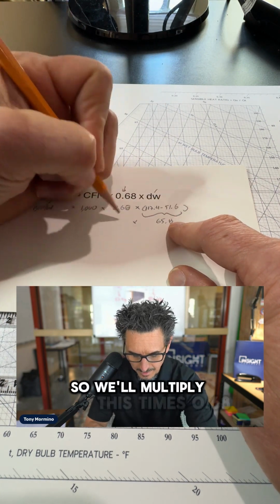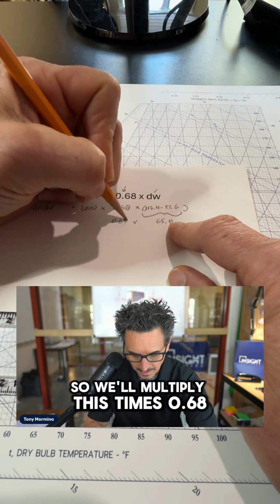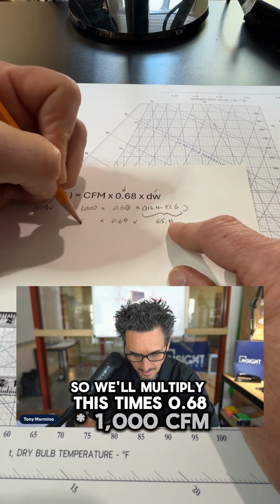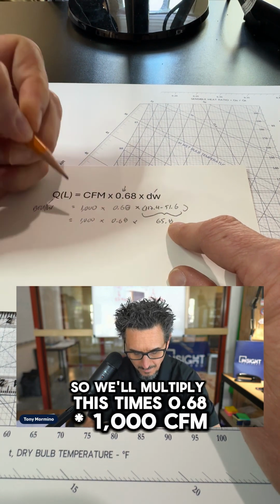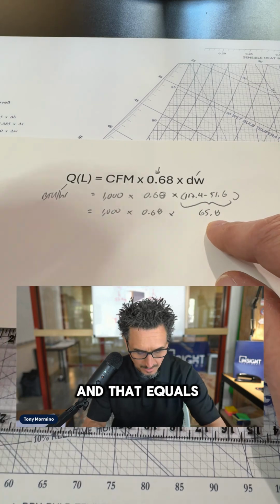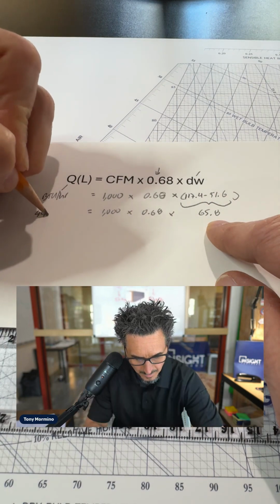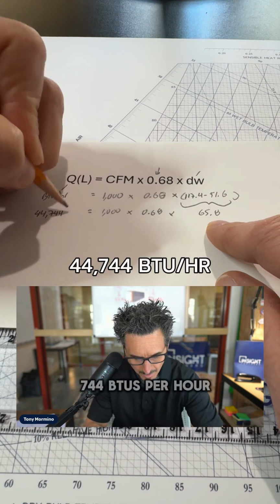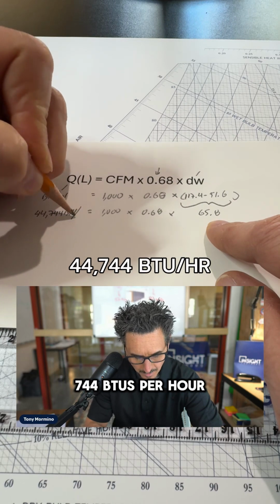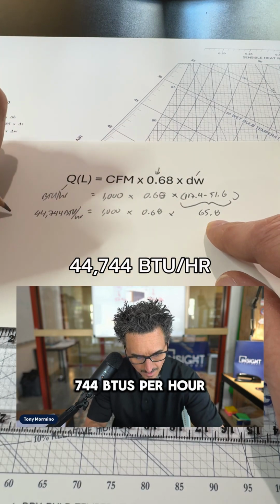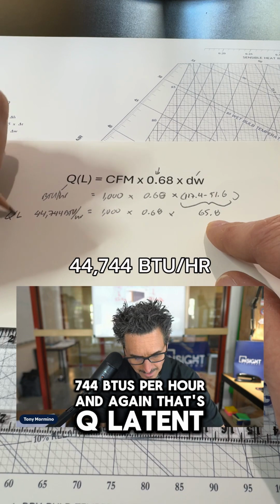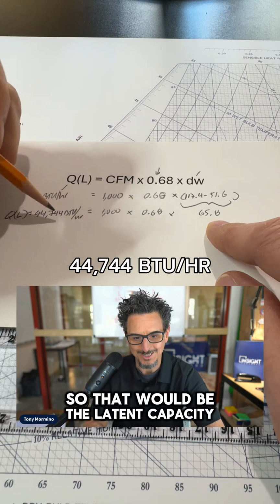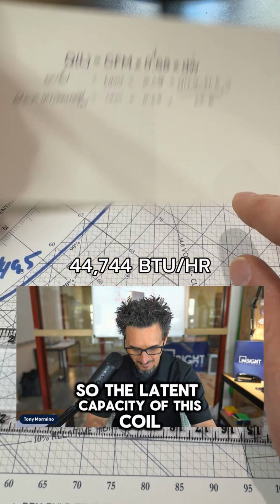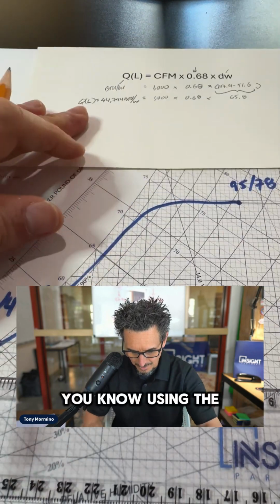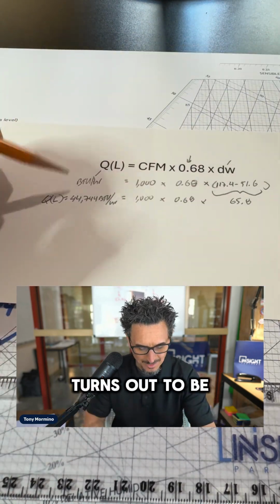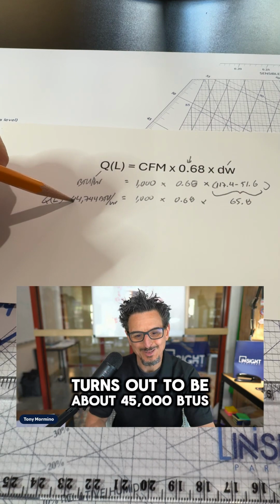So we'll multiply this times 0.68 times 1,000 CFM, and that equals 44,744 BTUs per hour. And again, that's Q latent. So that would be the latent capacity. So the latent capacity of this coil, using the psychrometric chart, turns out to be about 45,000 BTUs per hour.